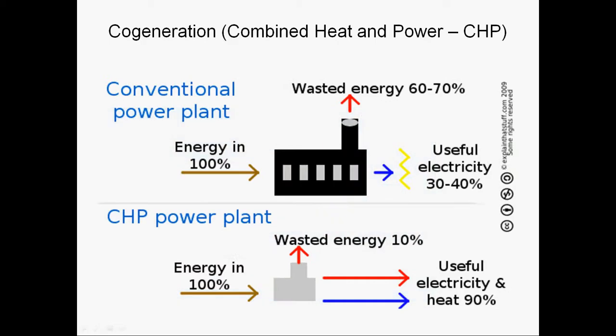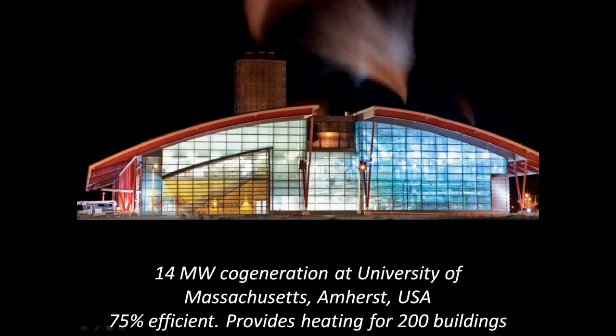Combined heat and power, or cogeneration, addresses the problem of waste heat by siting generation in places where industrial steam, heating, or even cooling is needed. The power plant's waste heat is captured and put to a useful purpose, vastly increasing the efficiency of fuel use — going from about 30 to 40% up to about 90%. Cogeneration is widely used in the United States; here's an example at the University of Massachusetts that provides heating for about 200 buildings.